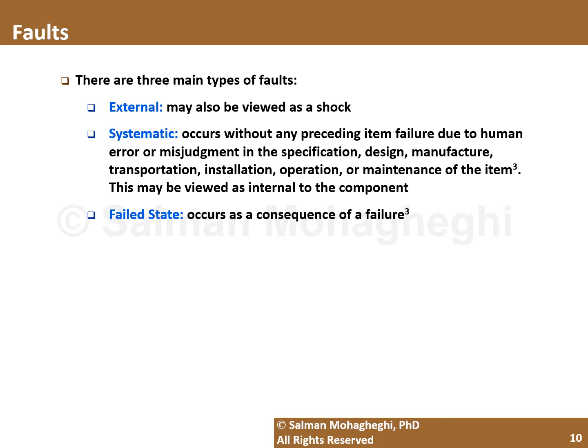Then we have systematic faults. Systematic faults occur without any prior item failure. Essentially, it's due to some sort of human error or any type of error during the design and specification of the component, during its manufacturing stage, transportation to the site, installation, operation, or maintenance, for example. These types of faults can be viewed as internal to that component or to the system. Some examples could be design errors, installation errors, or software bugs. The third category is the failed state. This is essentially a fault that is a consequence of a failure, and I'll talk more about that on the next slides.